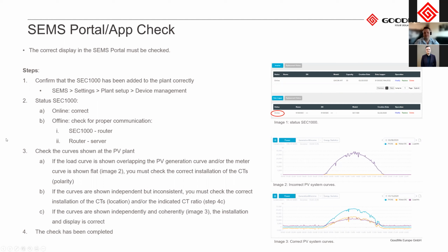So what we're checking on the SEMS portal is whether the production or the load curve is following the production. That could mean that either our CTs are incorrect or we haven't done our configuration correctly, because the load curve should not be following. As you can see in the bottom right corner, we should be able to see meter data at night where the PV is not producing, so you can see the load usage of the customer properly. And if we are exporting, we should then see our loads versus our export. If any of this doesn't look correct, then we might have to fault find our CTs to make sure everything's correct. So it's always very important, after you've done the installation, to check the next day or so, just to make sure that everything is displaying properly on the portal.